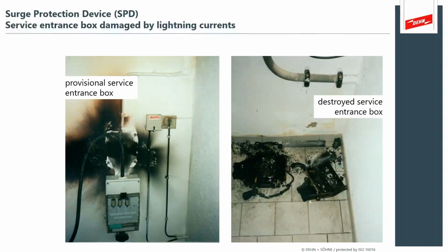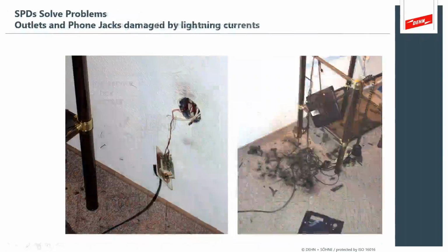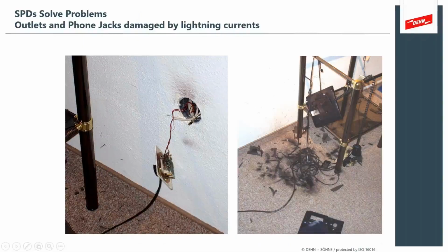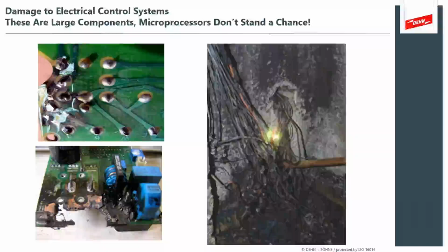What is the surge protection doing? It's preventing the voltage from sparking across what should have been bonded. So you can't bond your electrical power, but you control the voltage. When the voltage gets out of control, it gets out of the wire. And this has destroyed service entrance boxes. This has destroyed power wall outlet and data line coupling circuits. This has destroyed telephones and started fires. You have lots of examples from your own world where you actually can't even find what burned out, but your printer's dead, and it happened during the lightning storm. So you know it burned something out, and now you get to go troubleshoot and replace your equipment.